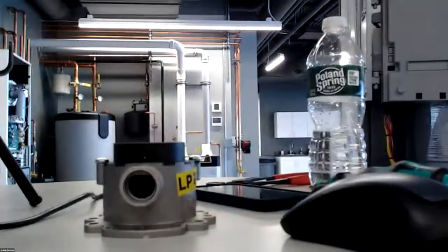Any questions? You good? Yeah, Josh, we had one that came through from Richard Scott. I'm just going to read this one as he's got it written here. From our experience on service and setup, we regularly see close to a 2-inch water column drop when testing at the gas valve. This is even with an indoor regulator being installed at the unit. We have verified pipe sizing to be more than adequate. Is this something that is normal to be seen on these negative pressure gas valves?